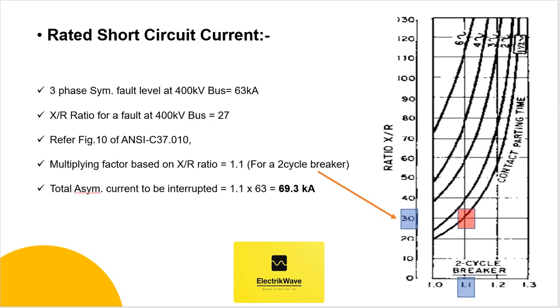Now let's calculate the rated short circuit current of the circuit breaker with the following inputs. The three-phase symmetrical fault level at 400 kV bus is 63 kA. The X by R ratio for a fault at 400 kV bus is 27, as per the system study report.